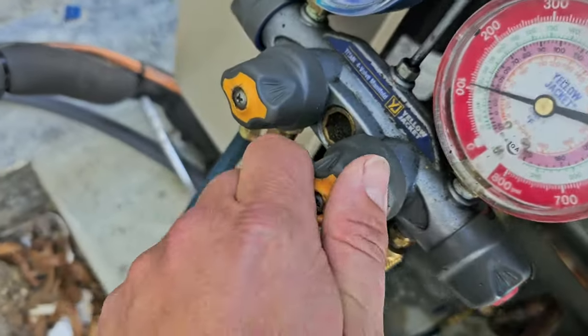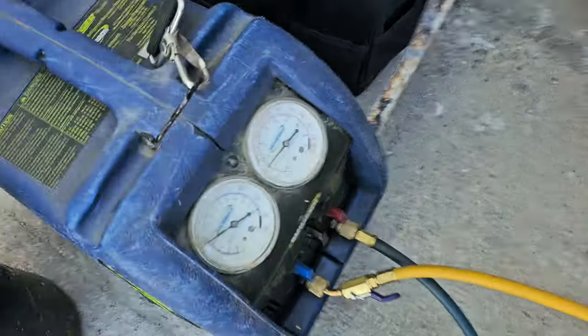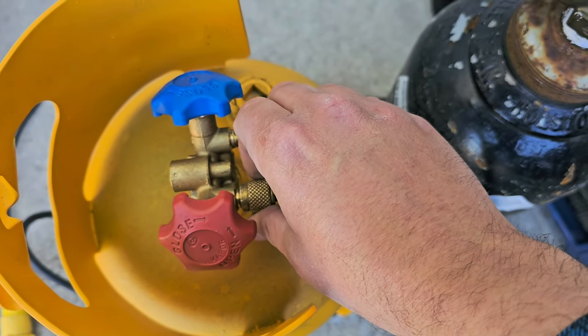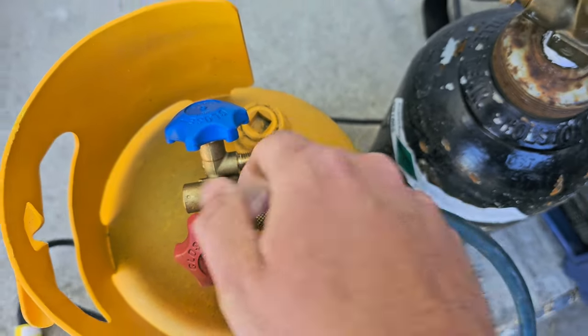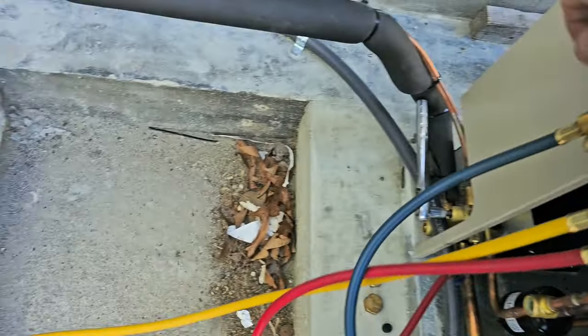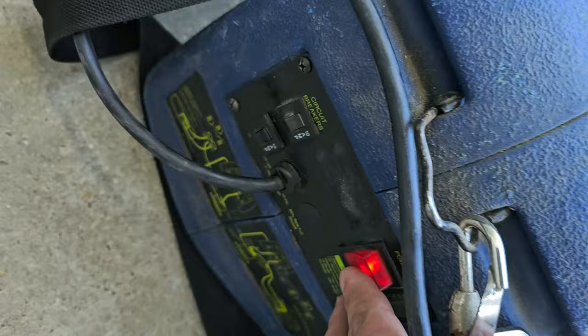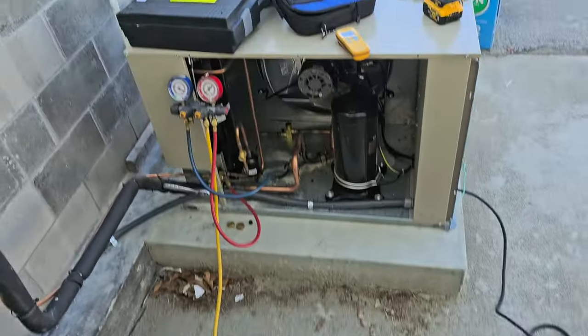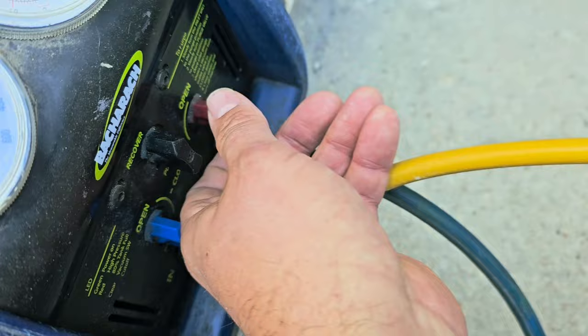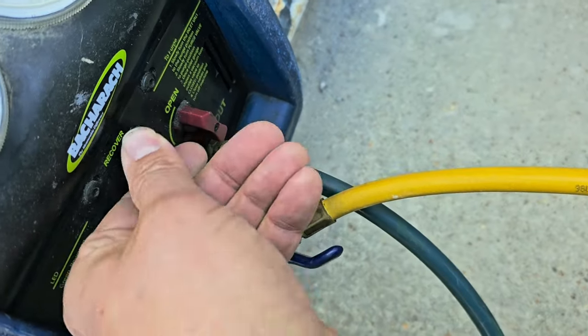Zeroed the scales. Now open up. Once I open it up, this is open in and out. I'm going to bleed this — I don't want a bunch of air in there. Now we're ready. Disconnect is on. Let's recover some refrigerant. That's good enough. I'm going to go ahead and push this to the out. Close that. Purge.